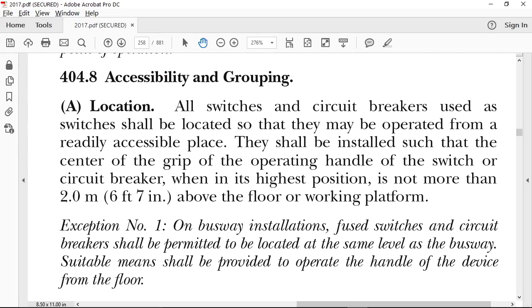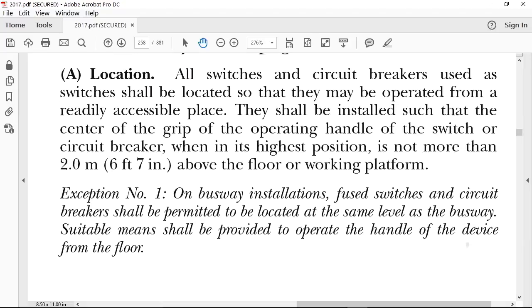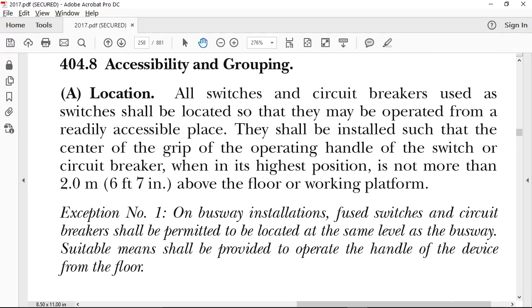Let's look at 404.8(A) and see if there's a reason. All switches and circuit breakers used as switches shall be located so that they're operated from a readily accessible place. So you can get to it. The center of the grip of the operating handle, with the circuit breaker in the on position, shall be installed no higher than 6 feet 7 inches. Okay, give me an example where you have a problem locating a switch above that.